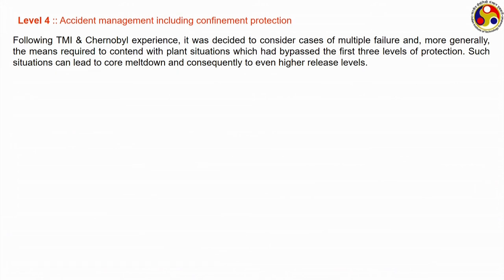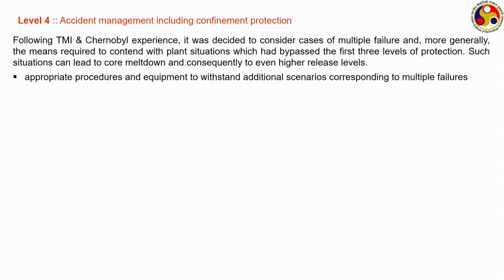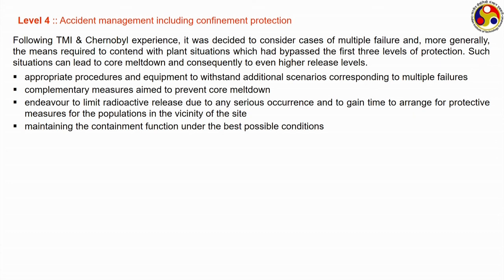The fourth level involves accident management including confinement protection — the final barrier preventing release of radioactivity to the surroundings. Following TMI and Chernobyl, it was decided to consider cases of multiple failures that bypass the first three levels of protection. Such situations can lead to core meltdown and even higher release rates. Appropriate procedures and equipment must withstand additional scenarios corresponding to multiple failures, with complementary measures aimed to prevent core meltdown, limit radioactive release, and gain time for protective measures for populations near the site.